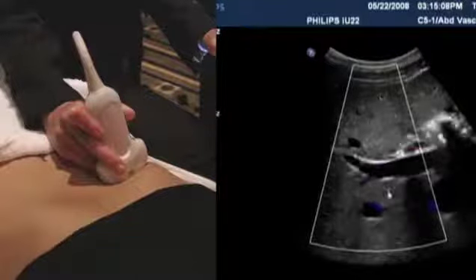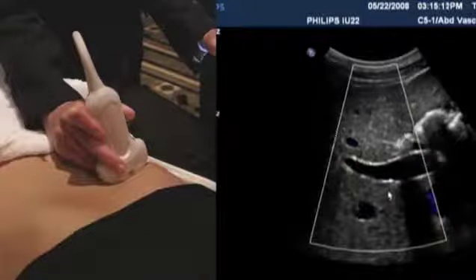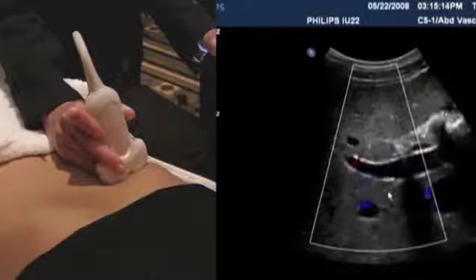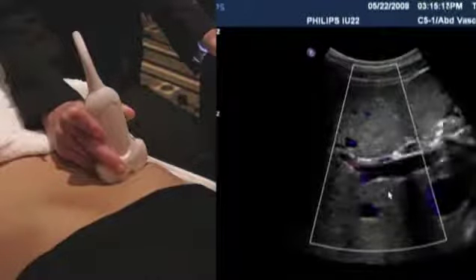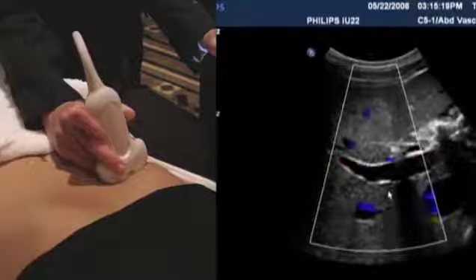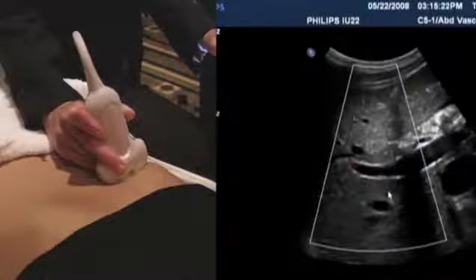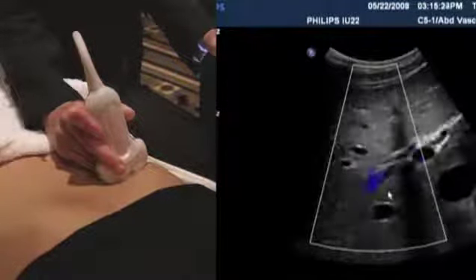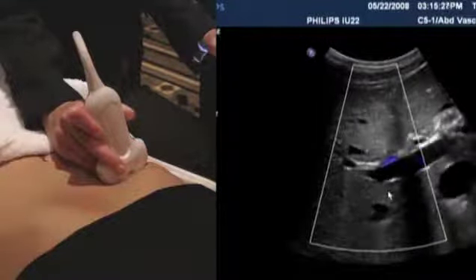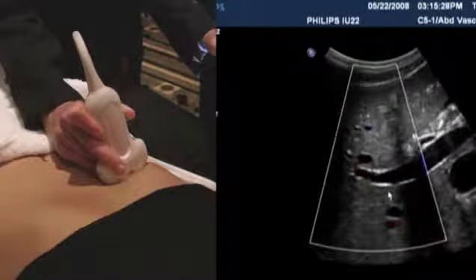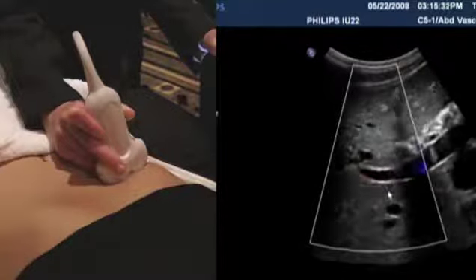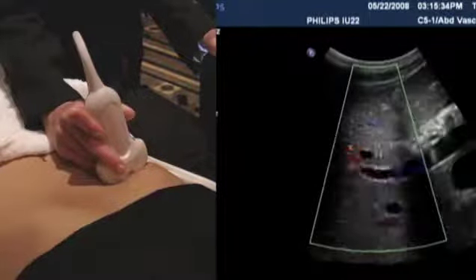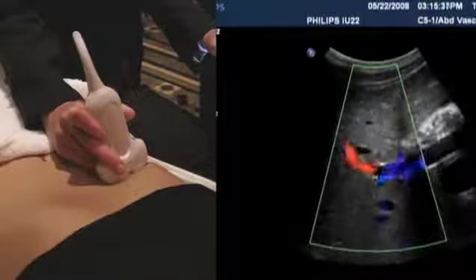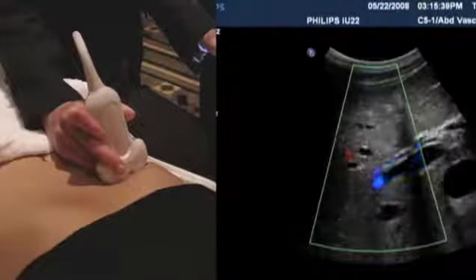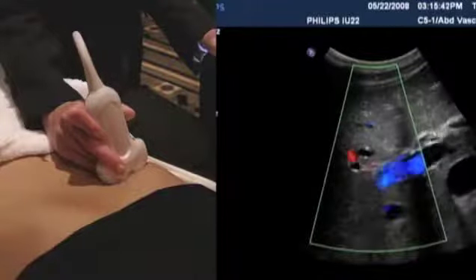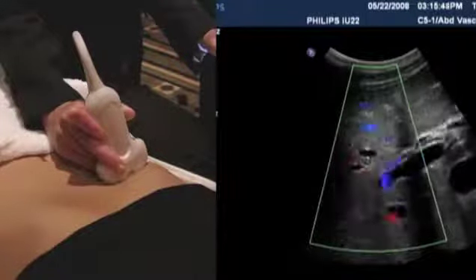So when you see that, you have a couple of options. You could turn the scale way up and see if that helps. And it doesn't always. You can choose the power Doppler mode of imaging rather than the pulse Doppler. Where's power? Oh, well, this machine has an upgrade, and I didn't know anything about directional color power. But anyways, so it shows the direction as well as it will be more sensitive. It's not as angle dependent. So it will pick up flow at 90 degrees.